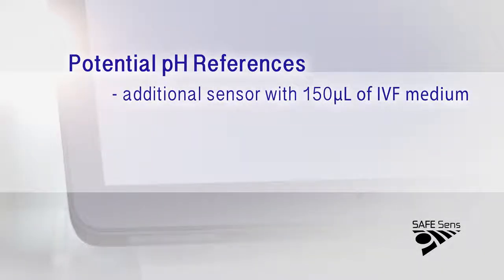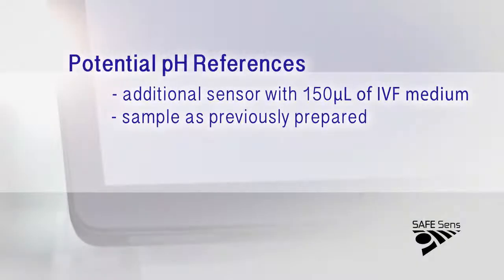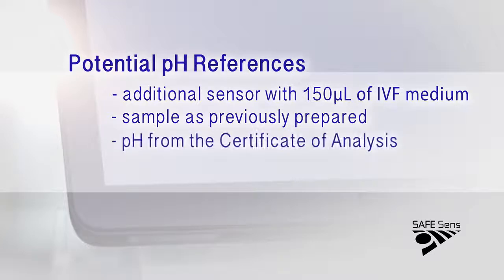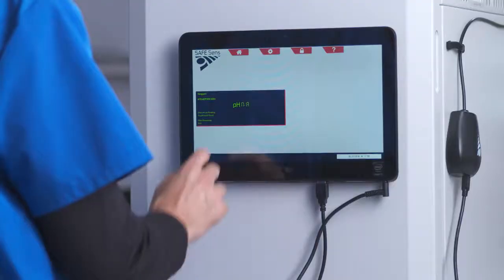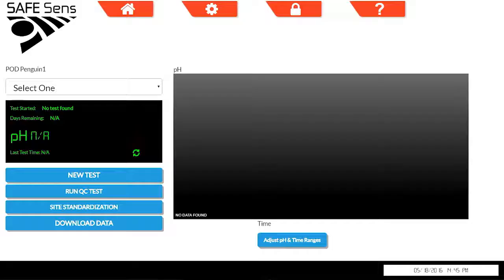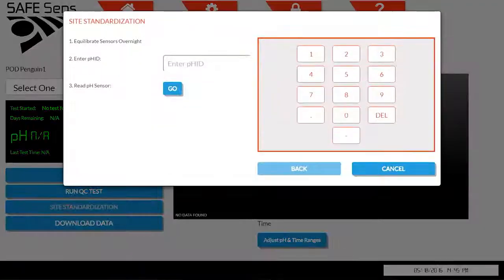You will also prepare a pH reference sample. This could be one additional sensor with 150 microliters of IVF medium to be used, which would then be read on a blood gas analyzer. Or it could be a sample as you would previously prepare for pH measuring in your lab. Or if needed, the reference could be the pH from the certificate of analysis when you duplicate the CO2 settings accounted for elevation. After the sensors have equilibrated for 24 hours, select the TrakPod you will test, then use the Site Standardization button. Enter the pH ID that is found on the blue packaging label of the sensors.